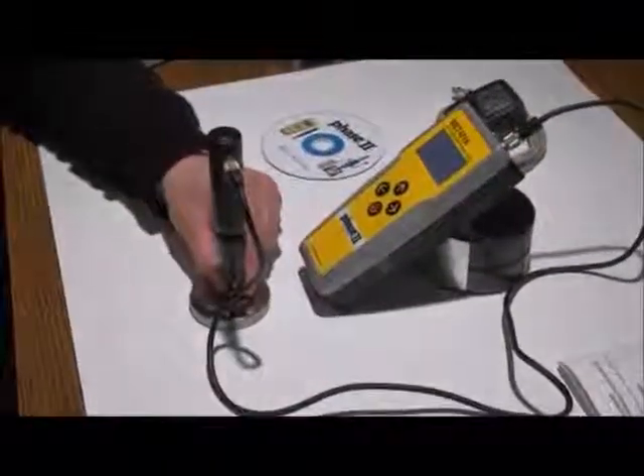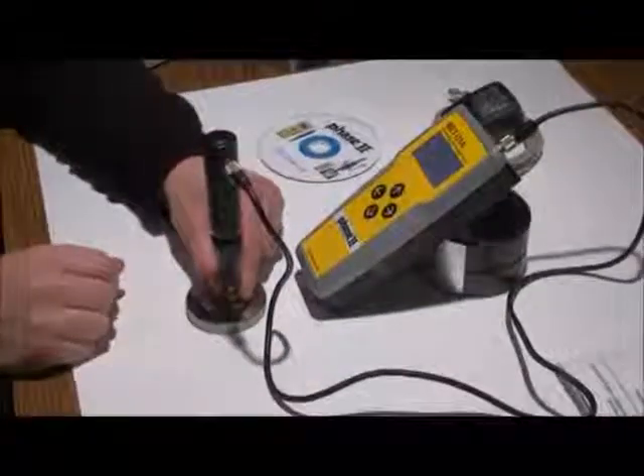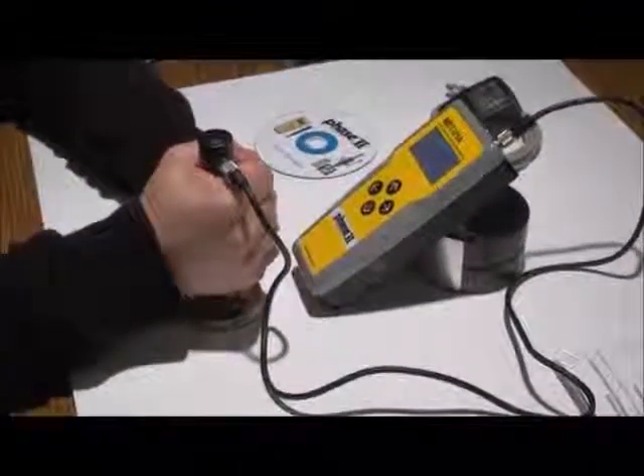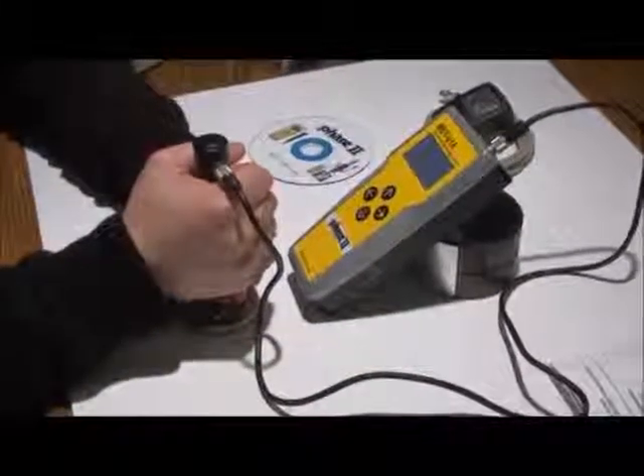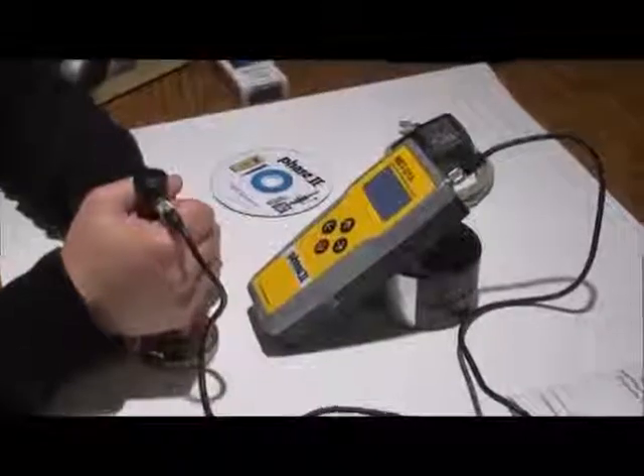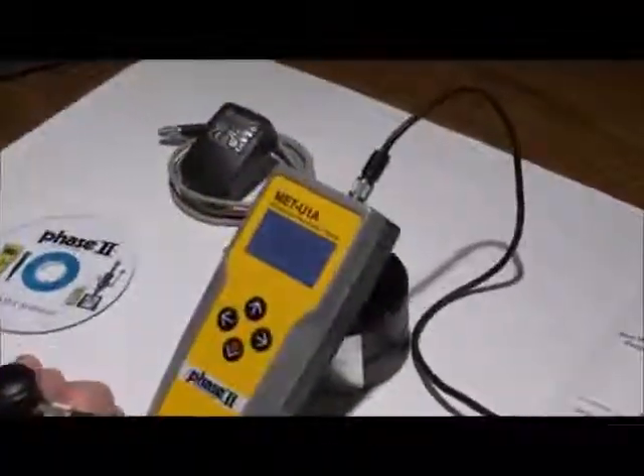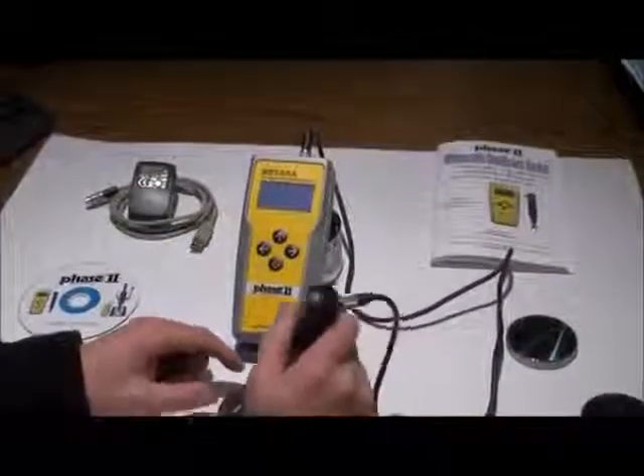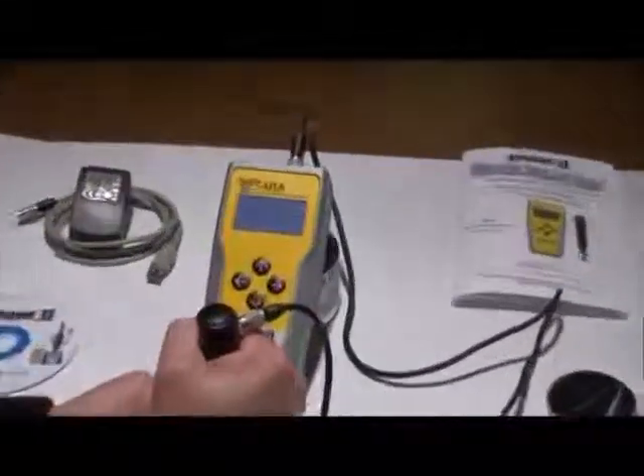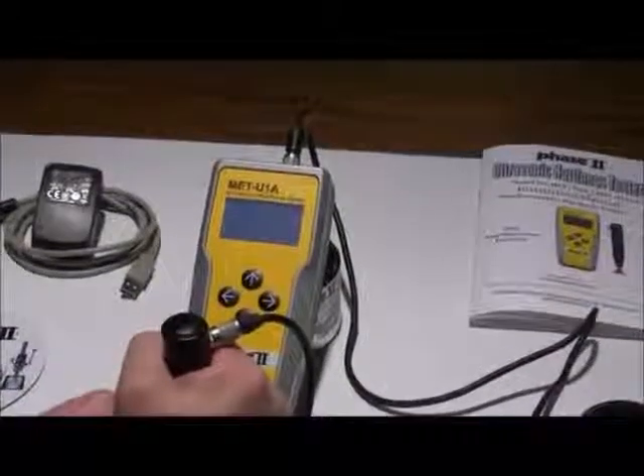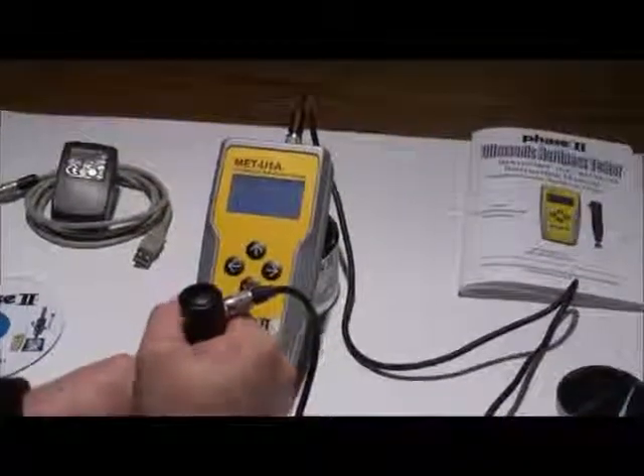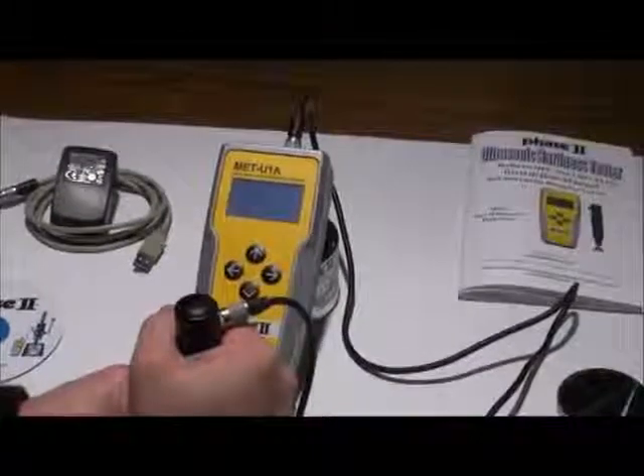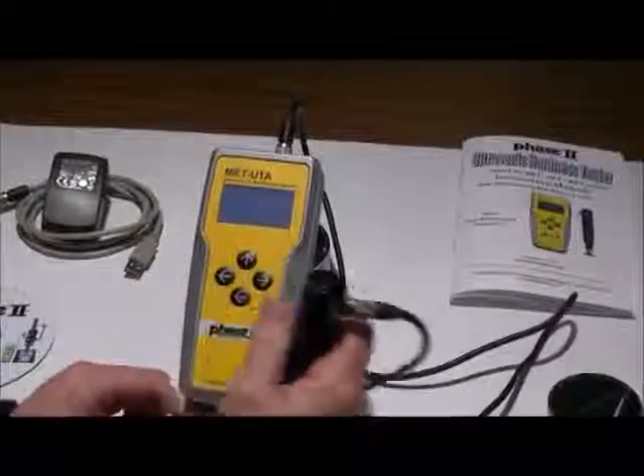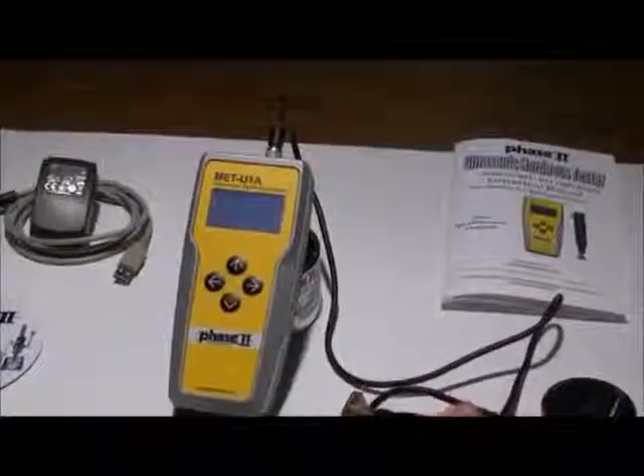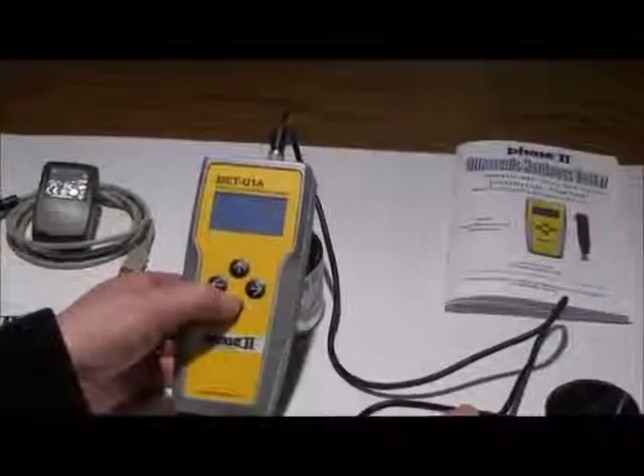With brass foot being held by 2 fingers, flush against your workpiece or test block, apply a given downward load to probe without any vibration or movement left or right. This takes 2 seconds until tone sounds and reading is shown. Let's take some tests and see the results. Pressing the down arrow button after 5 readings will give you an average.